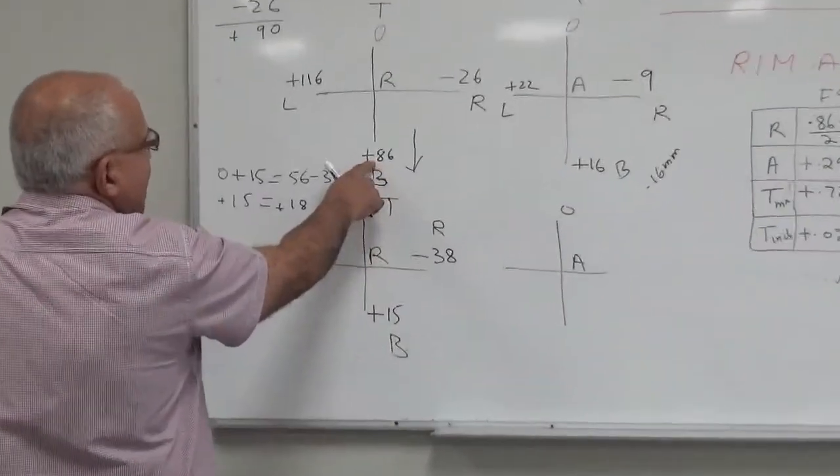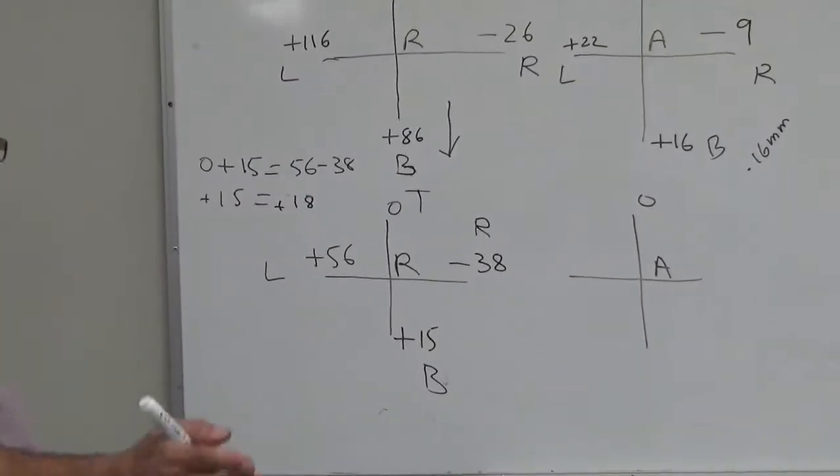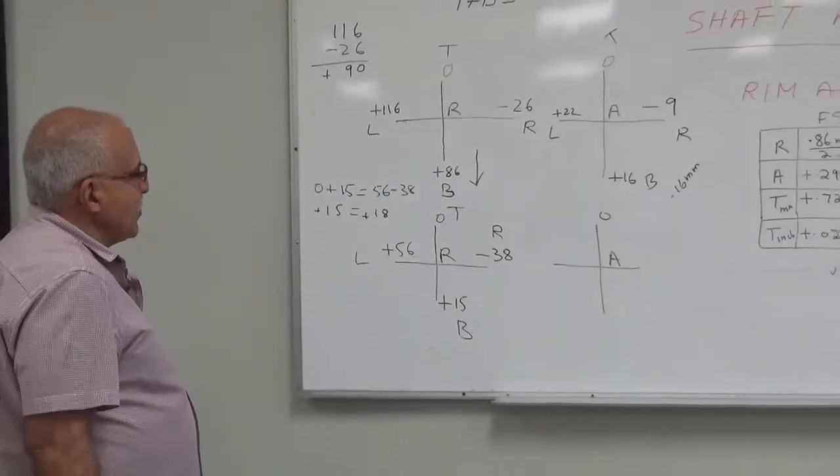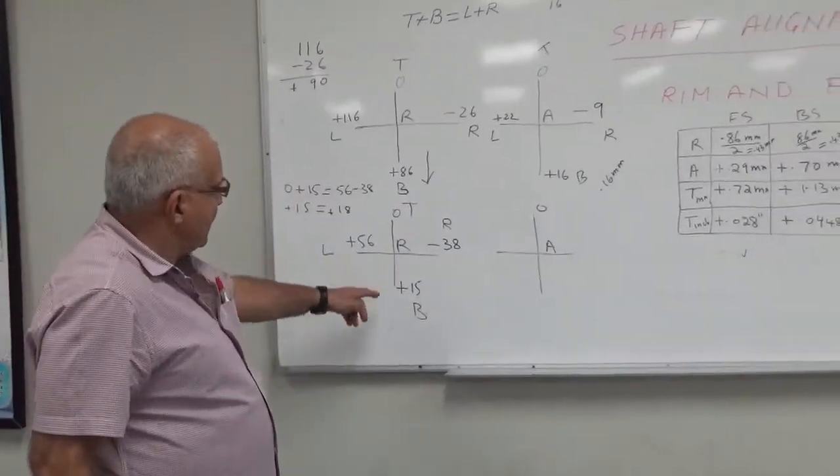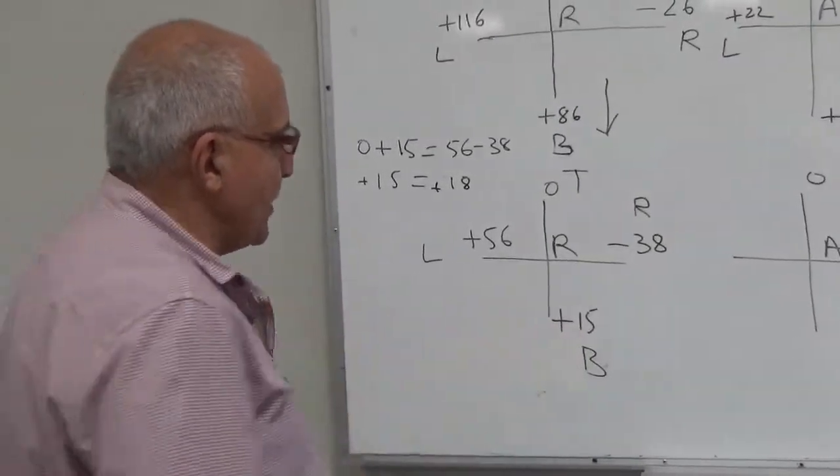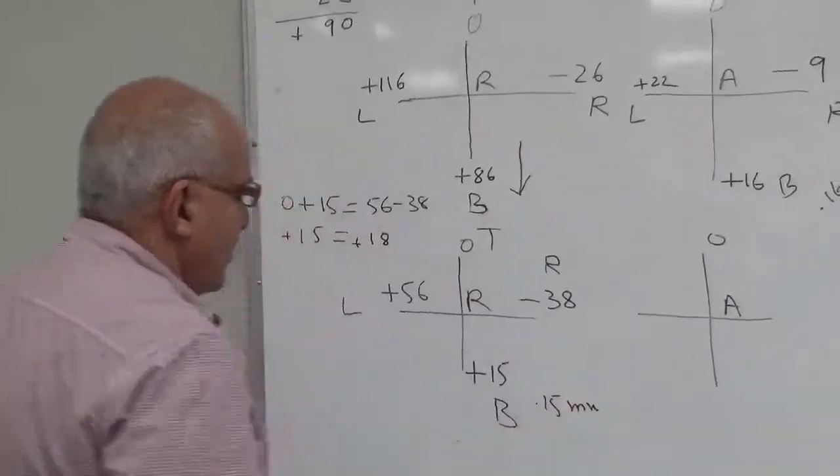So now my reading is plus 15. Before it was plus 86, so this is good reading for this pump. For example, if the speed of the motor is near about 2000, then total reading which is 0.15 millimeter is a good result for vertical alignment.